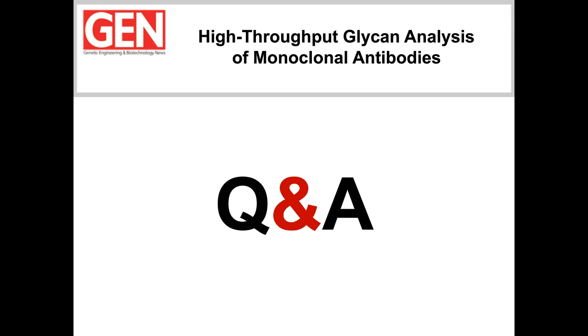So this can be either a small volume of highly concentrated IgG-containing media, such as 100 microliters of 1 mg per mL, or a larger volume of less concentrated IgG-containing media, such as 1 mL of 100 micrograms per mL. Just as long as the load volume doesn't exceed 1 mL, because that's the maximum load volume capacity for the Assay Map Bravo.